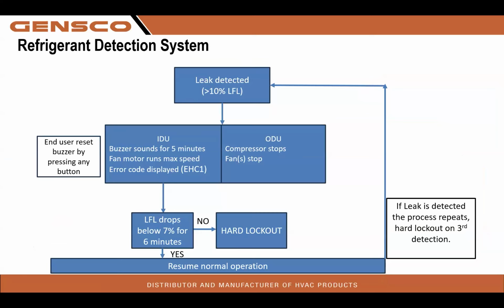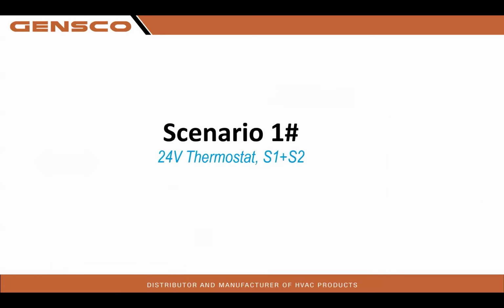Leak detection. In the event of a leak, the sensor is going to detect that leak. The buzzer will sound for 5 minutes. The fan motor will run at max speed, and an error code of EHC1 will be displayed on the 7-segment display. The compressor will not run, and if the LFL drops below 7% for 6 minutes, it will restart normal operation. If not, you will be in a hard lockout. If a leak is detected, the process repeats, with hard lockout on the third detection.